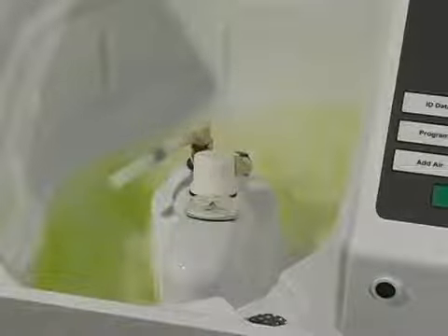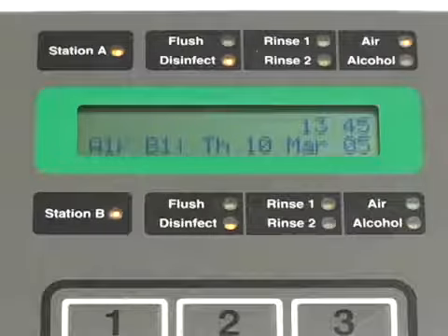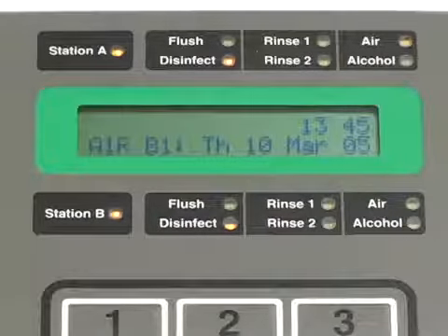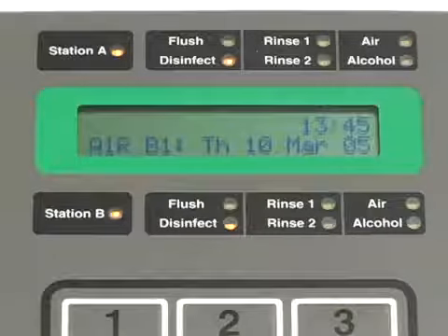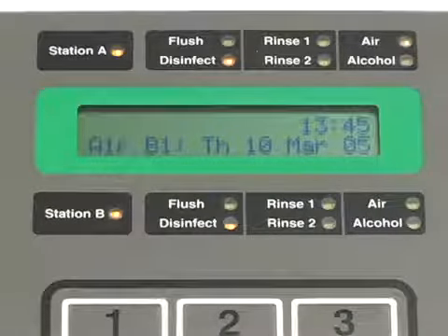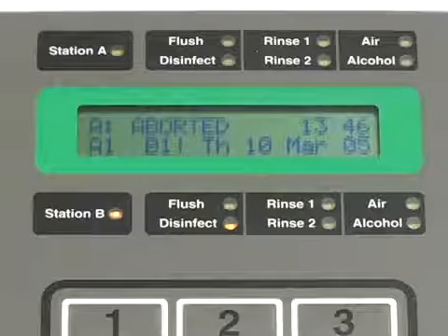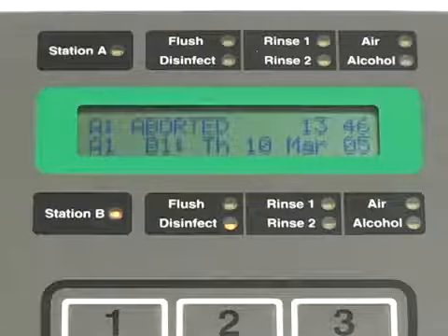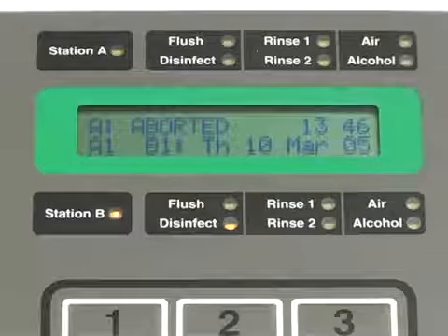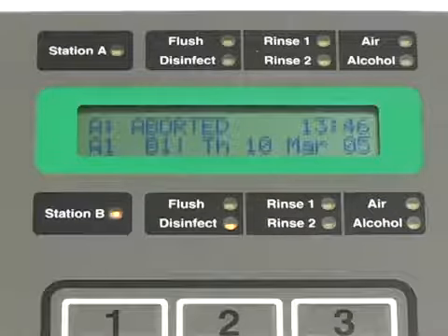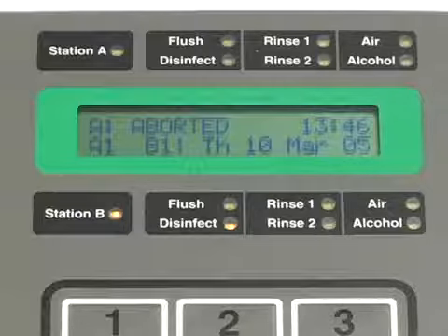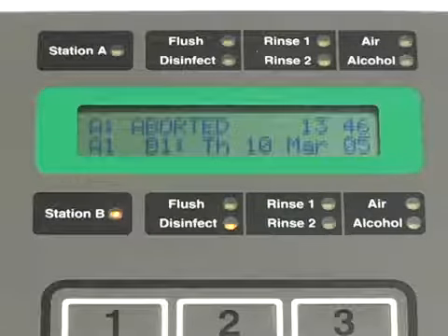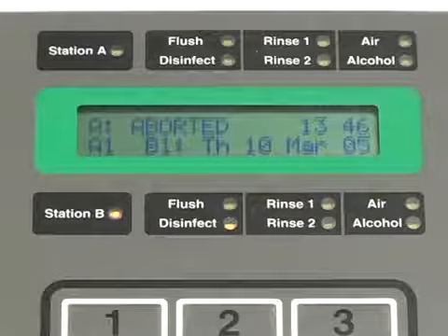Repeat the filling procedure until 4 gallons of disinfectant are loaded. If you wait 10 minutes in total, Completed will appear on the control panel display. Alternatively, if you wish to speed up the process, press the Cancel key after the load cycle is complete, and then press the Enter key to start the automatic rinse of the basin. After completion, Aborted will appear on the LCD. Press Setup 16 to confirm the unit has reset the cycle count to 0. If it is not, enter Setup 11, which resets it to 0.